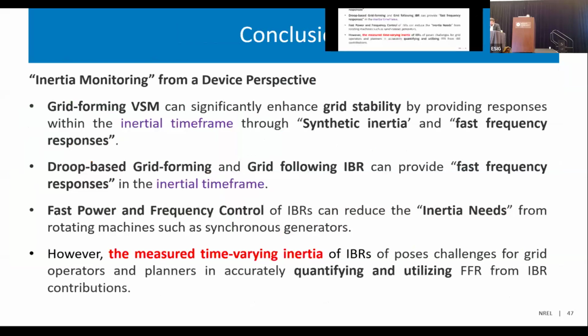This is still an open question for all of us, but let me quickly wrap it up from two perspectives. First, from a device level perspective, we have good news for inverter vendors: no matter whether it's a grid-forming VSM, a droop-based grid-forming, or a grid-following inverter, we found they do contribute faster response in the inertia time frame — whether you call it synthetic inertia or faster frequency response — and this reduces some inertial needs from traditional rotating machines such as synchronous generators, even synchronous condensers.